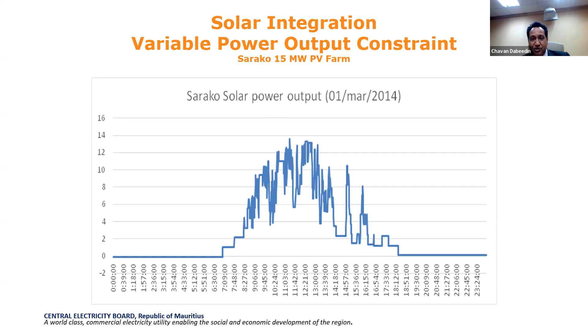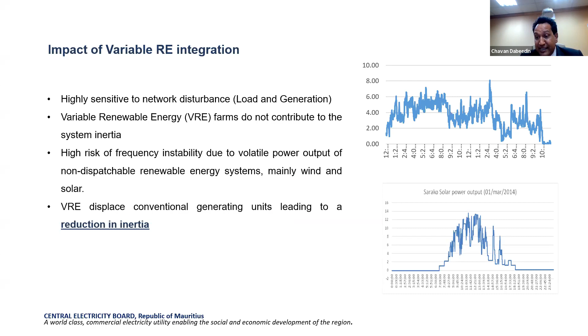So what happens is that variable renewable energy sources, which are highly sensitive to network disturbance, tend to affect the output and the frequency. So there is a high risk of frequency instability due to volatile power output. The VRE also displaces firm power, leading to a reduction in the system inertia. In Mauritius, our set frequency is 50 hertz, and we tend to deviate plus or minus 0.5 hertz. We are an insular power system, not connected to other countries, and we need to adhere to the range of frequencies.